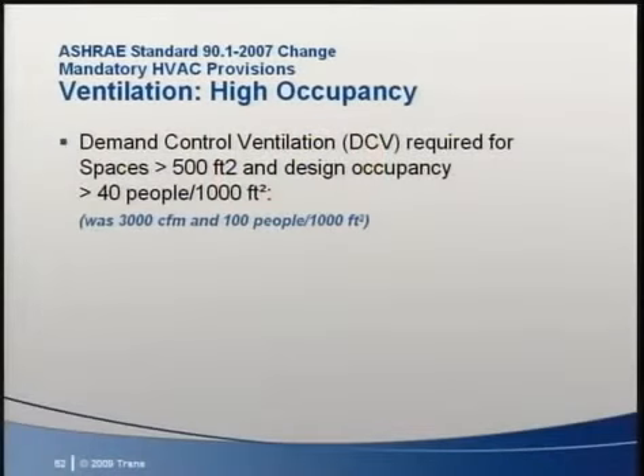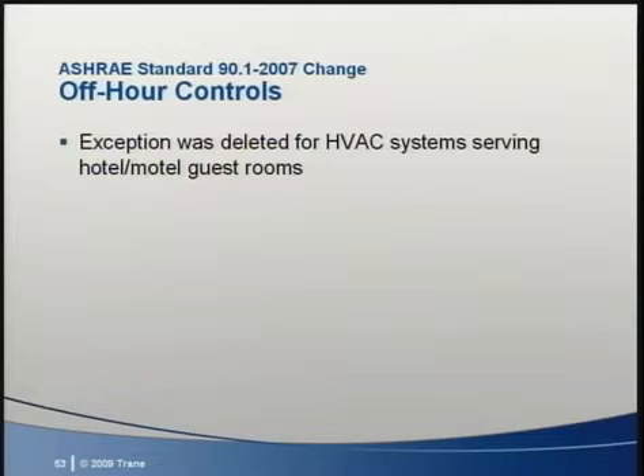On our last E&L broadcast, we spent quite a bit of time covering demand-controlled ventilation. The threshold for which DCV is required for a space was reduced and now applies if the space is more than 500 square feet and the design occupancy is greater than 40 people per 1,000 square feet. In the controls section of 90.1, an exception that used to exclude hotel and motel guest rooms from the off-hour controller requirements was deleted.